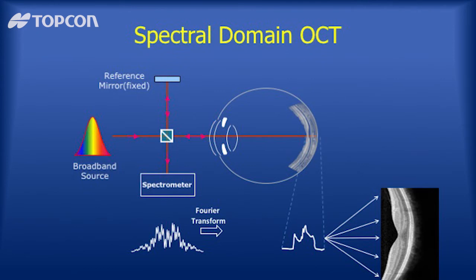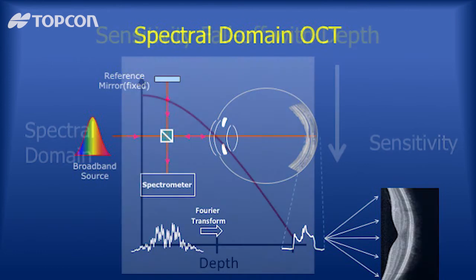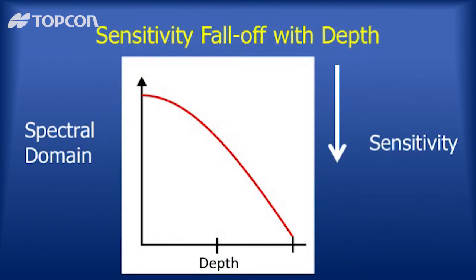Spectral domain OCT has many different reflections going on all at once, so the interferogram is fairly complicated. But this can be decoded by a Fourier transform to make an A-scan, and many A-scans together make a B-scan. The ingenuity of spectral domain OCT is that everything is depth-encoded in terms of interferogram frequency, but this is also a weakness, because in spectral domain OCT the detection method is not sensitive to high-frequency interferograms, causing a fall-off in sensitivity with depth.